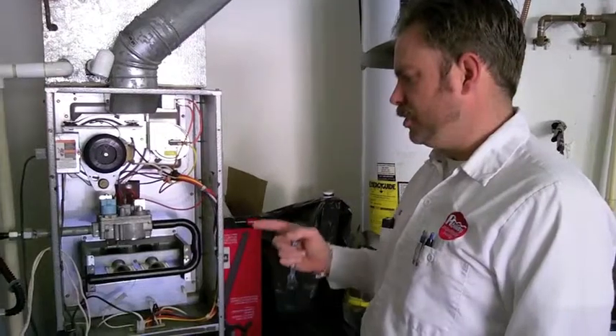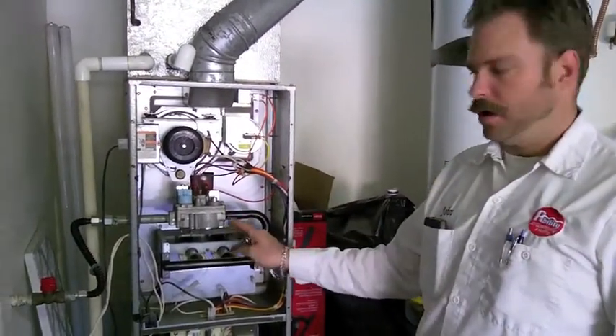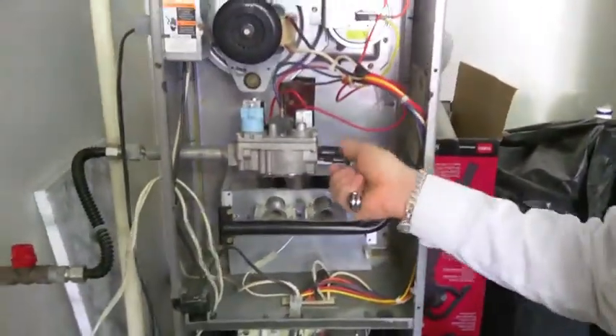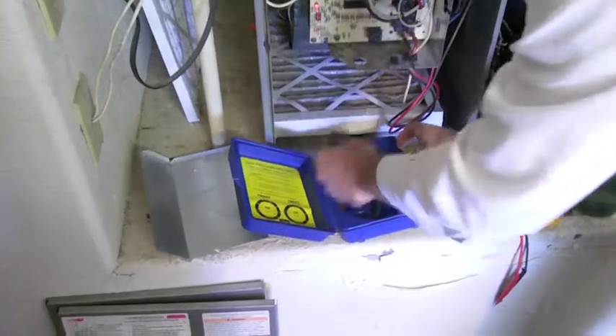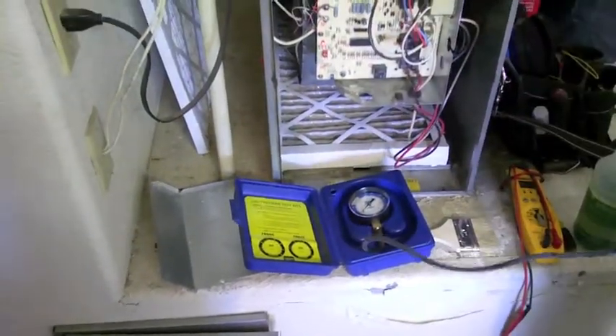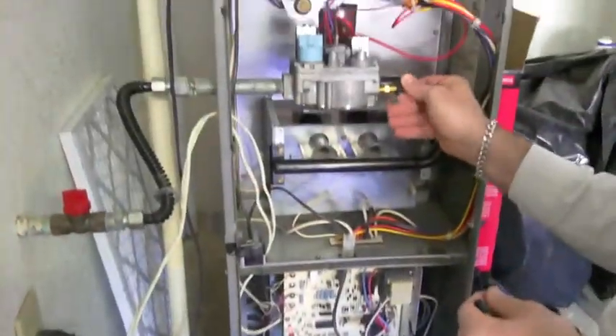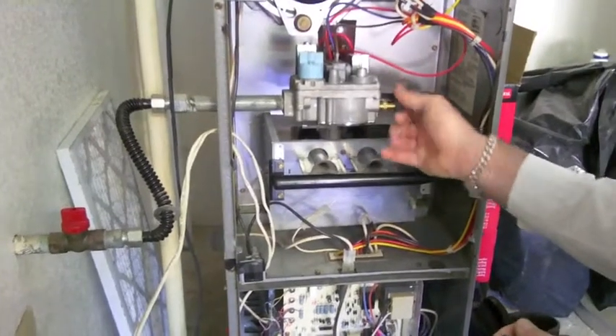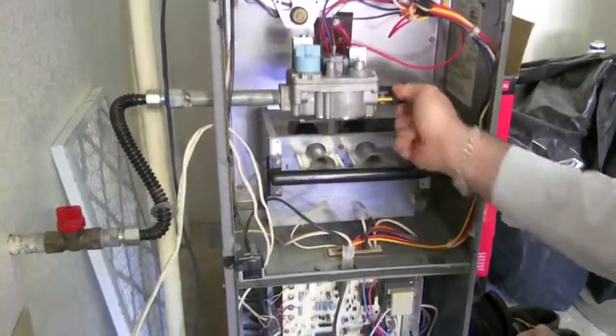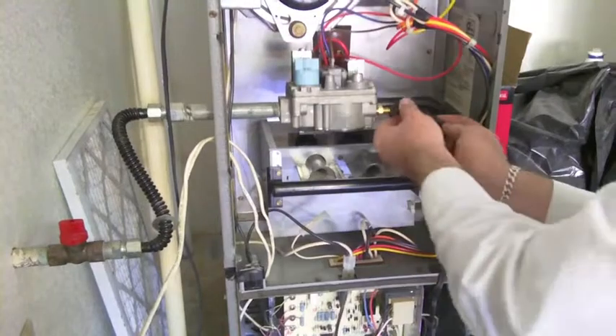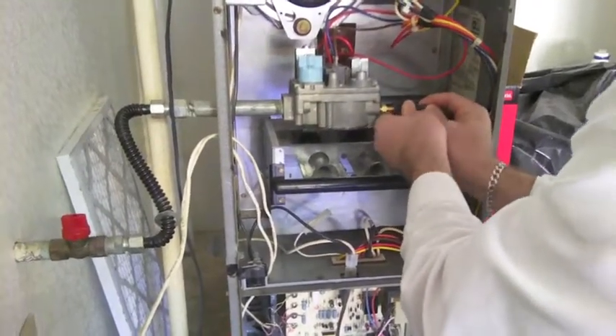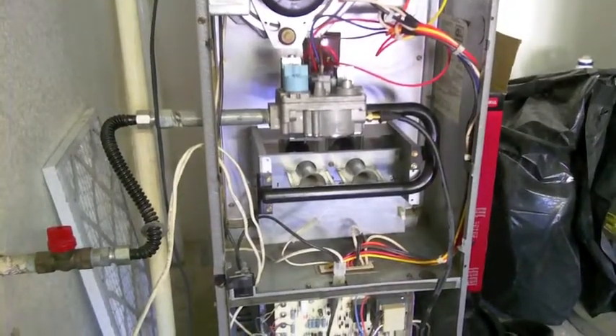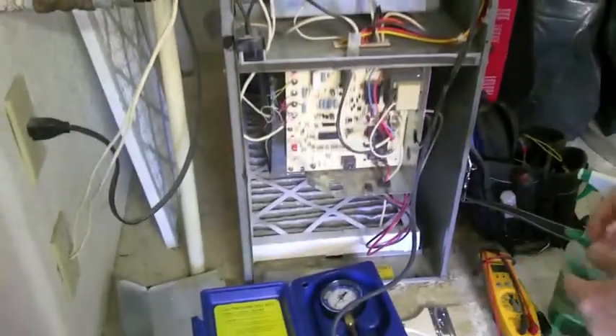Alright, so now we're going to check the gas pressure on the valve. So we're going to take this one off with a little Allen wrench. And here's our gas pressure tester. There's that. Now we can start the furnace.